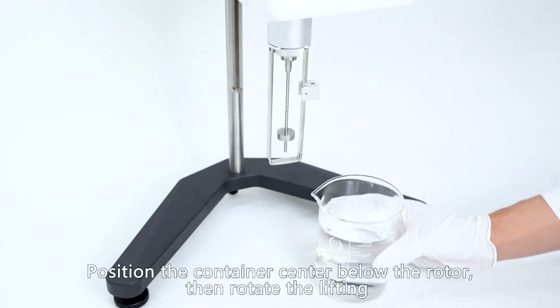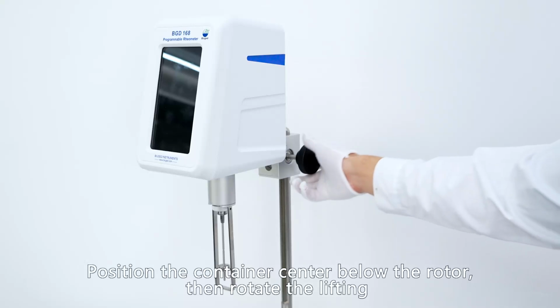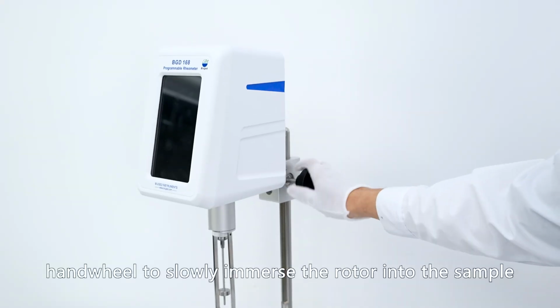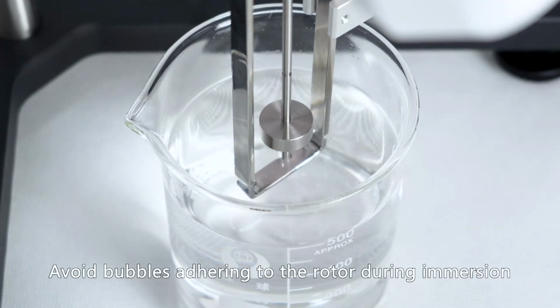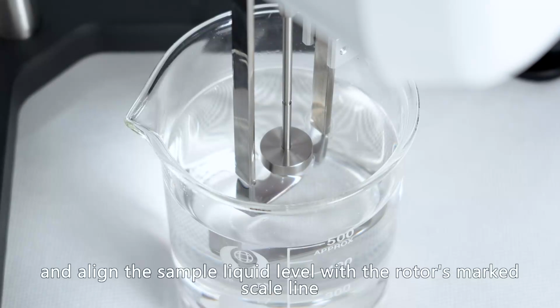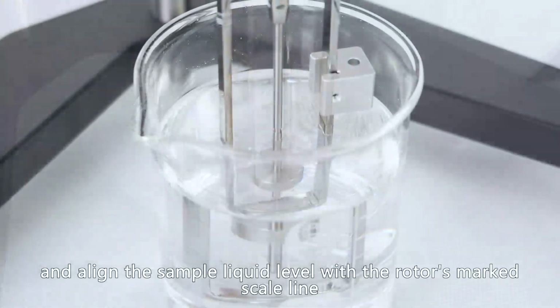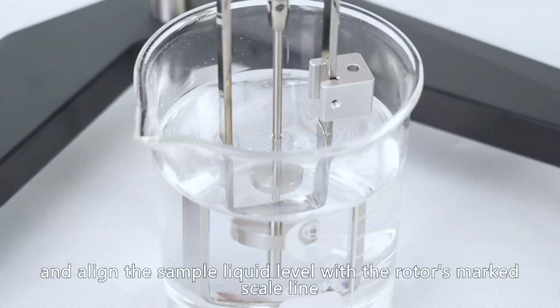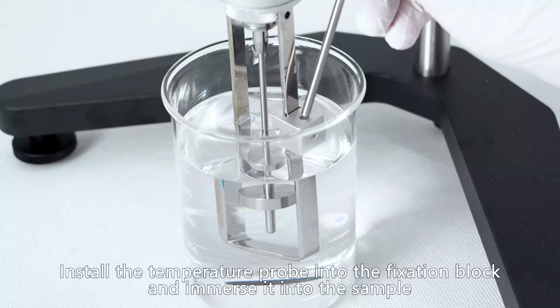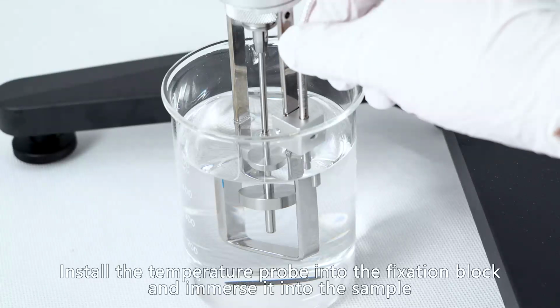Position the container center below the rotor, then rotate the lifting handwheel to slowly immerse the rotor into the sample. Avoid bubbles adhering to the rotor during immersion, and align the sample liquid level with the rotor's marked scale line. Install the temperature probe into the fixation block and immerse it into the sample.